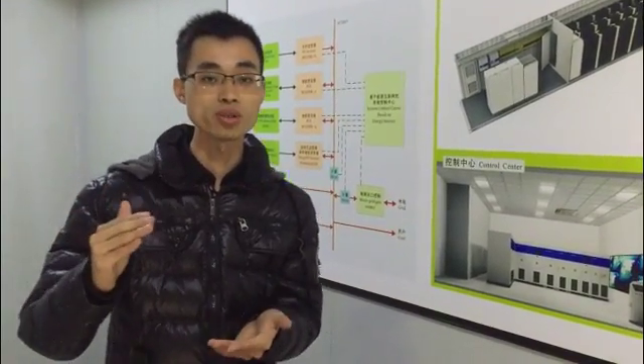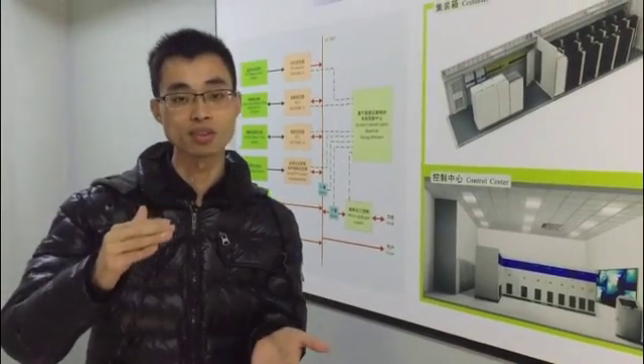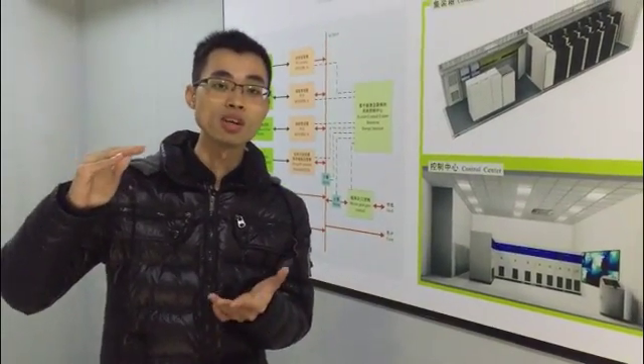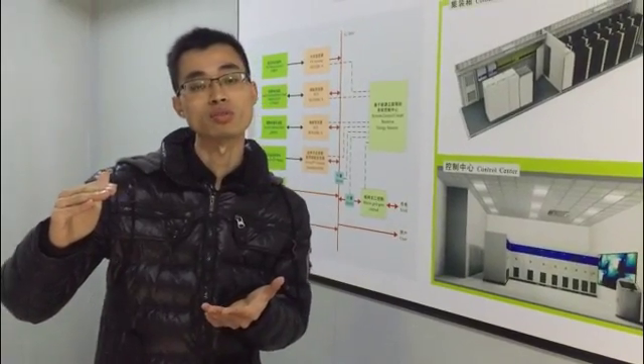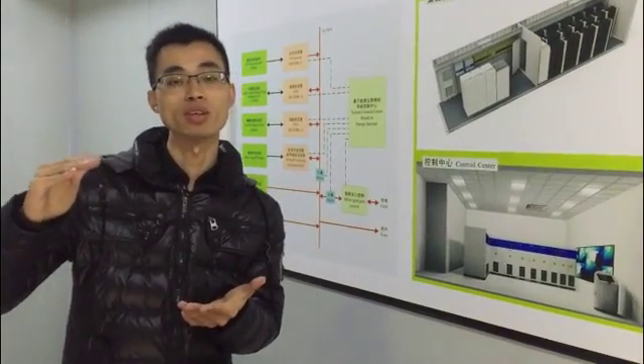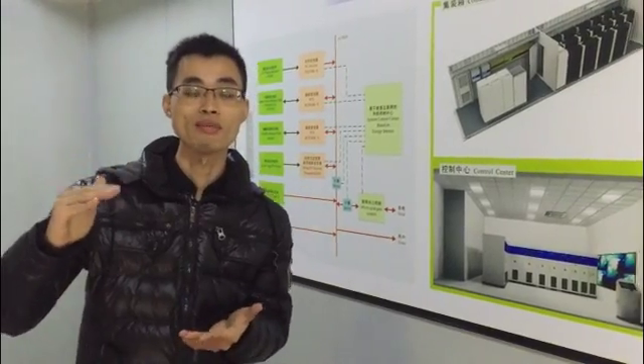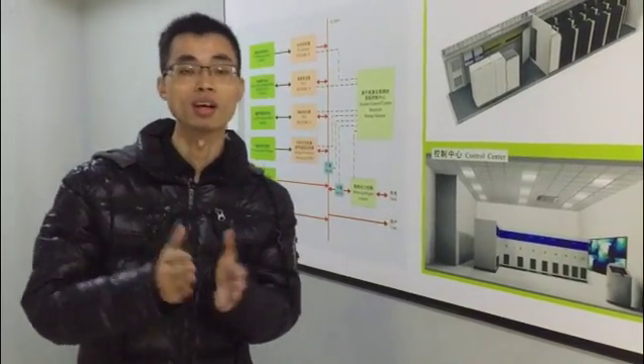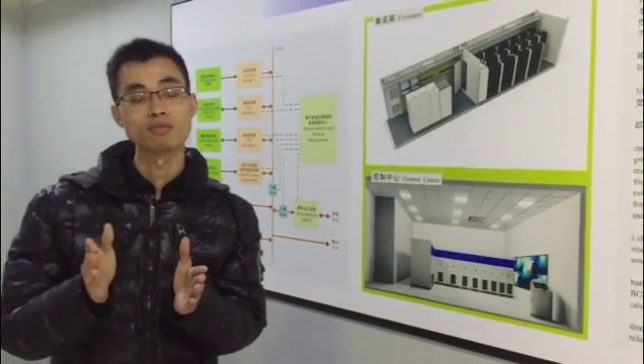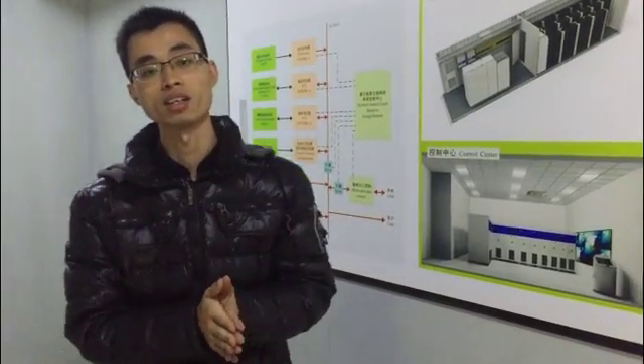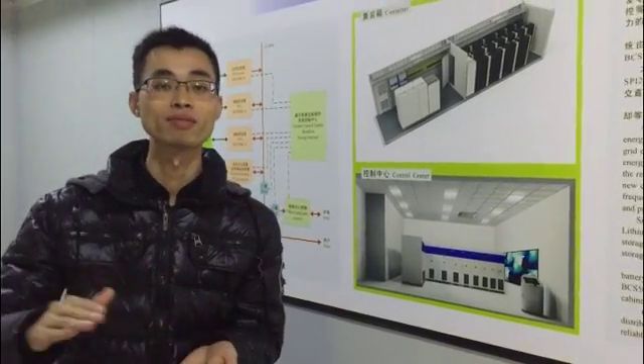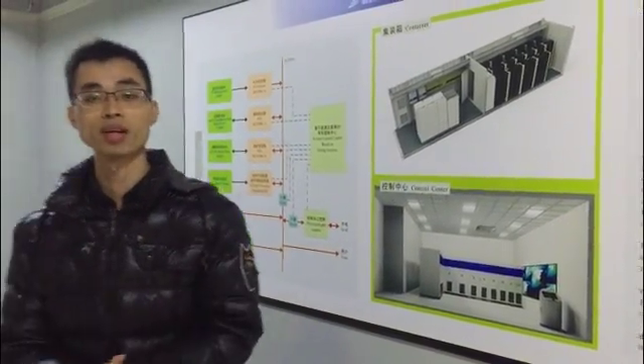This is very important for the system. But for the normal lead acid battery or gel battery, if the SOC is always at 50%, it will reduce the lifetime to a very low level. So I think lithium battery is better for your frequency regulation system. But our lead carbon battery is okay to use in a commercial system, like a factory system, for peak shaving. So this is our microgrid system.